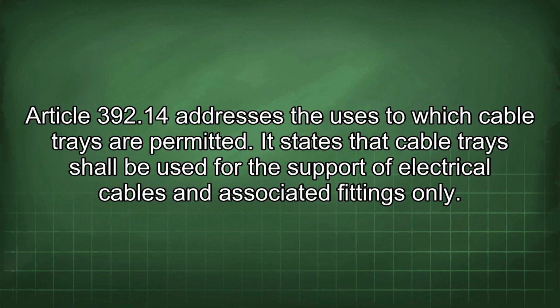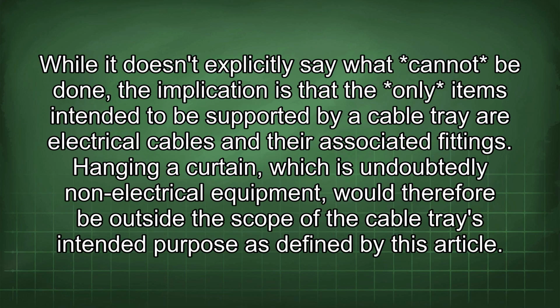Article 392.14 addresses the uses to which cable trays are permitted. It states that cable trays shall be used for the support of electrical cables and associated fittings only. While it doesn't explicitly say what cannot be done, the implication is that the only items intended to be supported by a cable tray are electrical cables and their associated fittings. Hanging a curtain, which is undoubtedly non-electrical equipment, would therefore be outside the scope of the cable tray's intended purposes defined by this article.